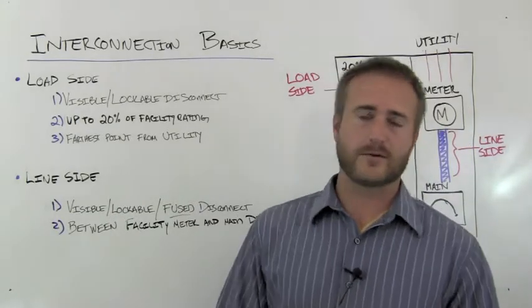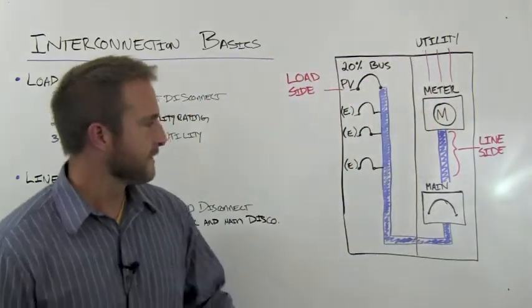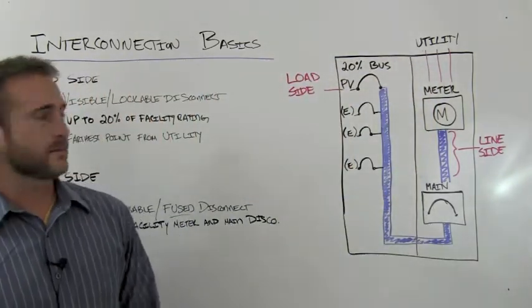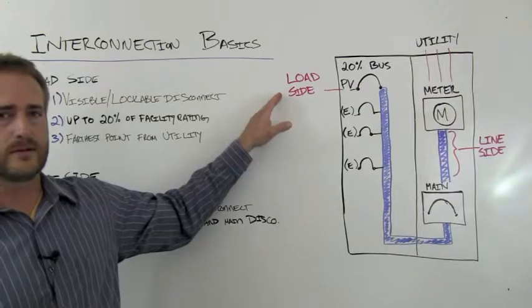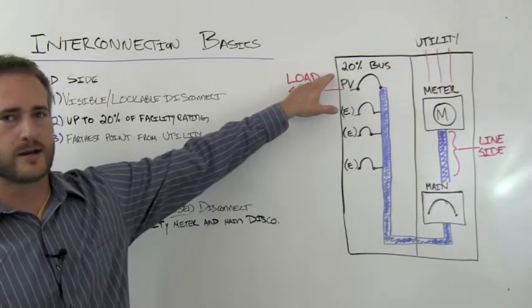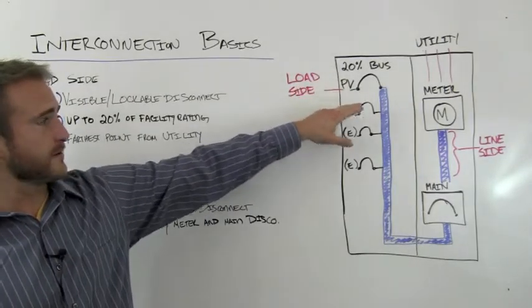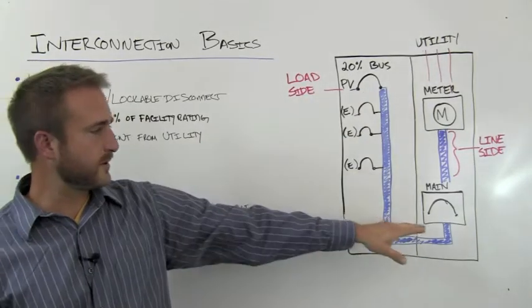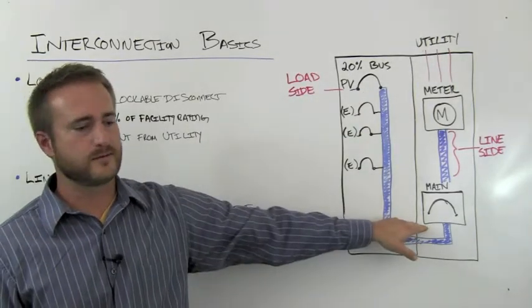And what that means diagrammatically, if this is your facility gear, for your load side connection, you can feed up to 20% of your gear's rating at a breaker farthest away from the point of utility feed on your bus.